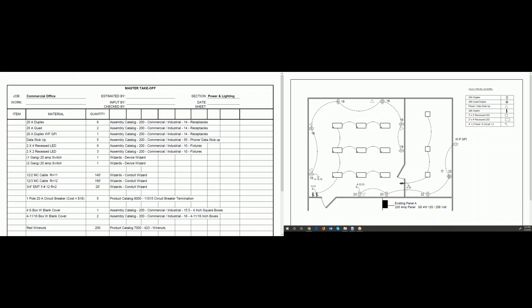I count all the duplex receptacles and list them on the takeoff sheet, then do the same for quads. On your handout, highlight the different components as you count them so you don't count them twice. We can see I've counted and input items on the takeoff page. I also took off conduit — there's 12-2 MC cable at 140 feet, and 12-3 MC cable at 190 feet on the takeoff page.